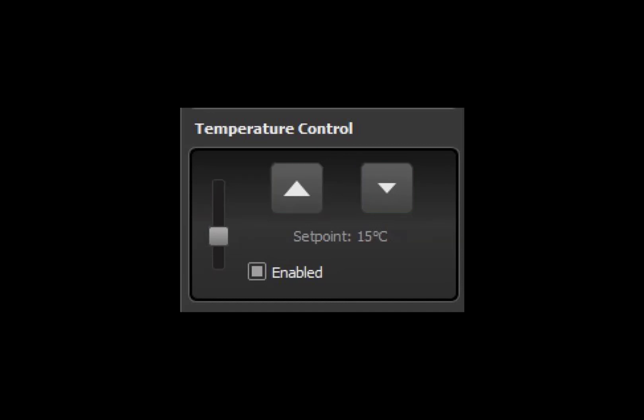It's not recommended that temperature control be disabled. However, the user has the option to do so if they wish to compare the baseline with and without thermoelectric cooling.